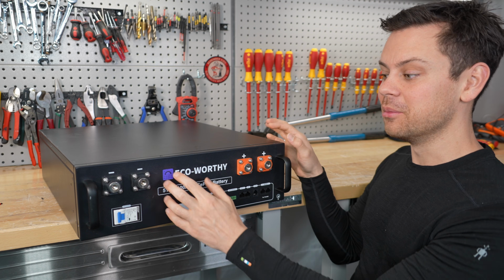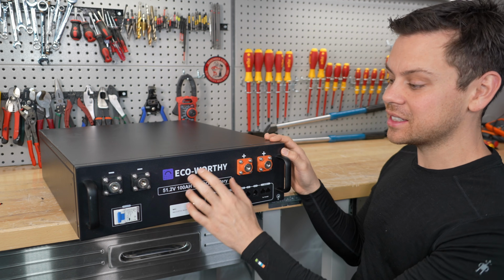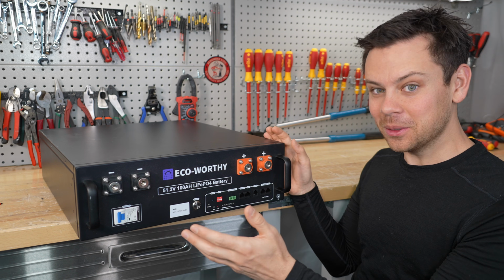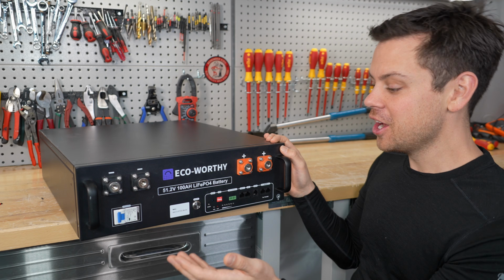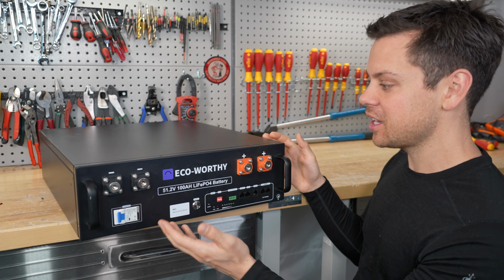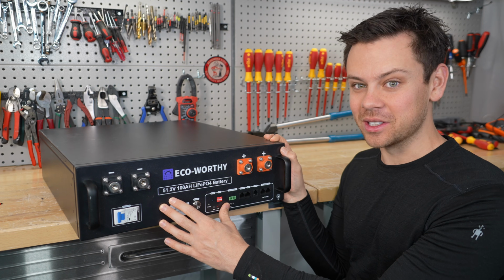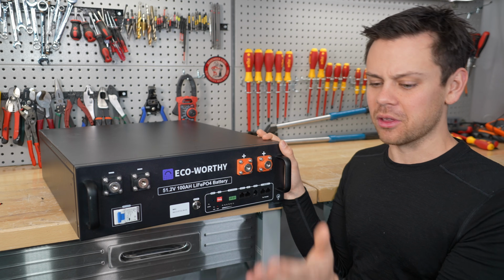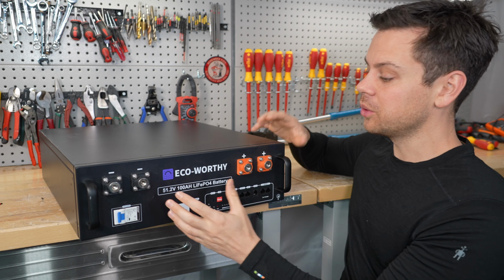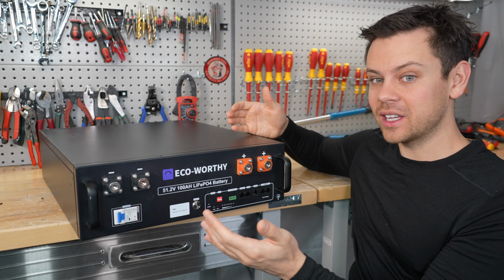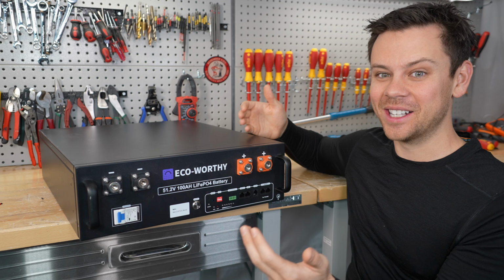Unless the cells have more capacity, in which case the cycle will instead be cut off by the coulometer, by the state of charge. So I did a discharge test with 60 amps continuous. All the other capacity tests were 3, 5, or 20 amps. In theory, at this higher rate, we should get less capacity, but guess what I got?